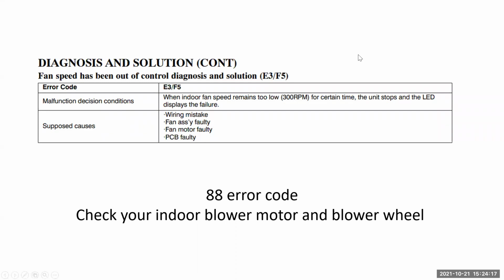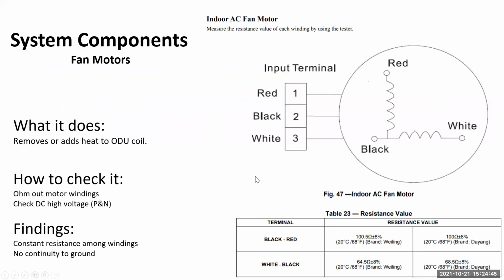He had replaced the indoor board earlier. So just to be certain, if you get that 88 code, it could be just the display, just everything lit up on it. So you also want to make certain your blower wheel spins freely. You want to check for resistance, and it's checked just the same way as we did the outdoor fan, the compressor. You want to refer to your service manual for the resistances. And once again, anything to ground, you want to replace that board. Not that board, that motor.